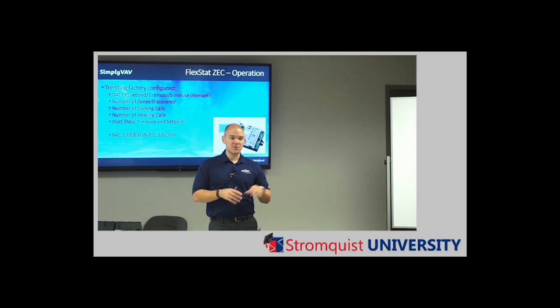That box is going to start to close. Maybe the 2 guys need a little bit of air, and they're going to fight each other the whole time. In a pressure independent application, I can guarantee that the 2 guys get the cooling that they need, and the 8 guys get the cooling that they need, and it's properly sized for the demand that's actually there.